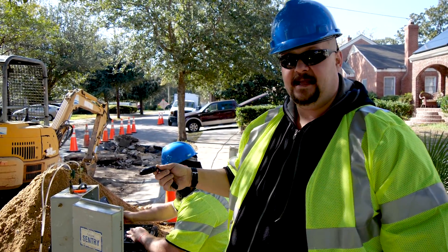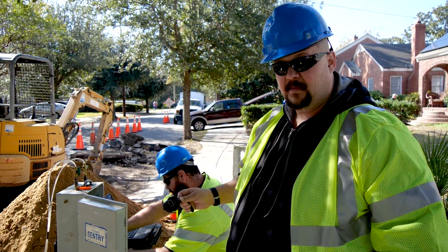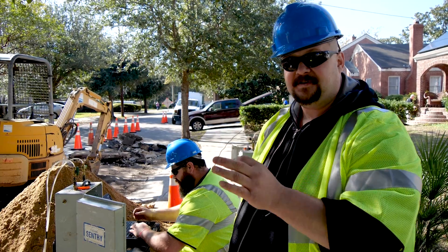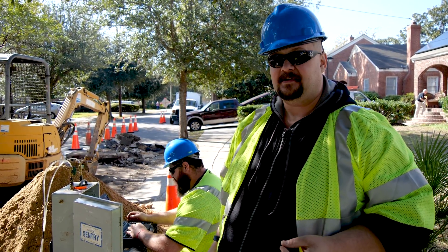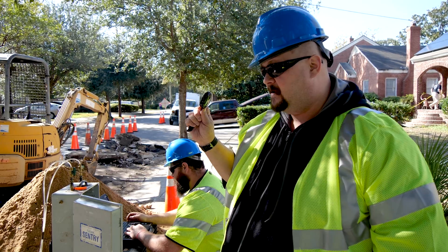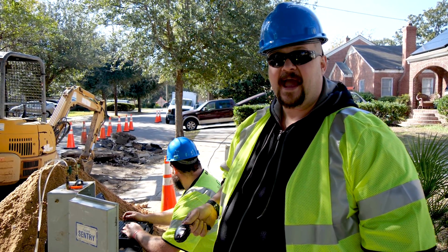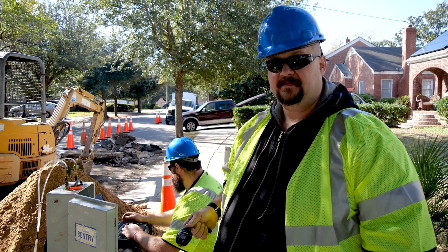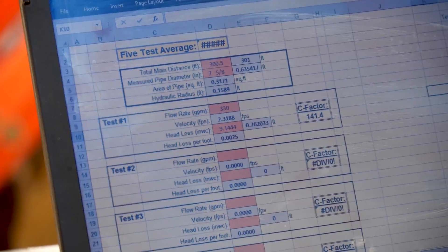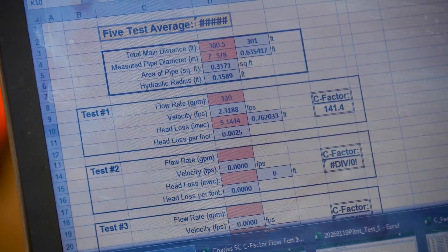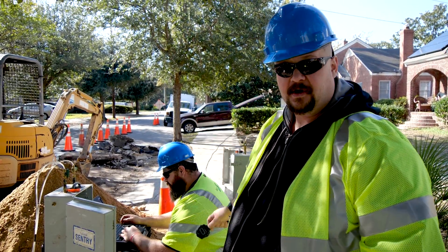We measure the velocity at different points within the pipe, then we download the data and use it to compute the average velocity across the pipe. It's kind of like a correction factor — it enables us to get flow measurement readings within plus or minus a percent or two. It's very accurate, and that's what we need for this type of testing. He's downloading the data and processing the velocity measurements while we concurrently run our first test.